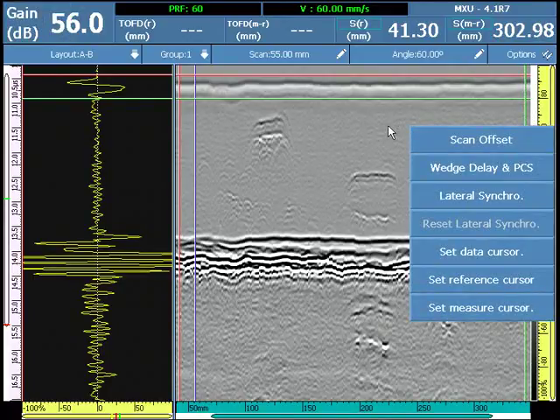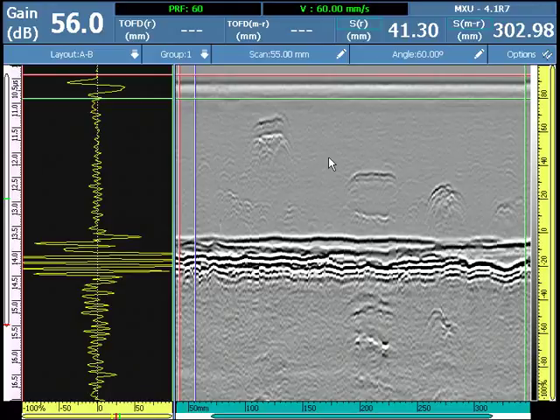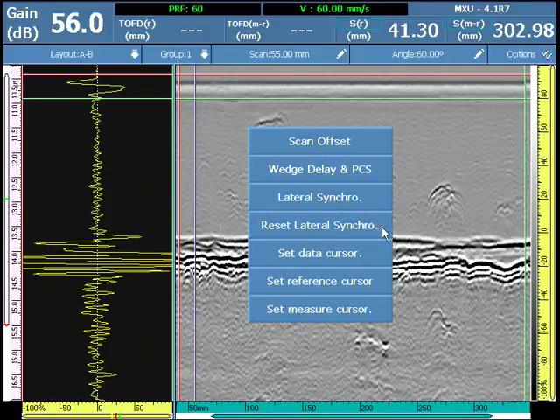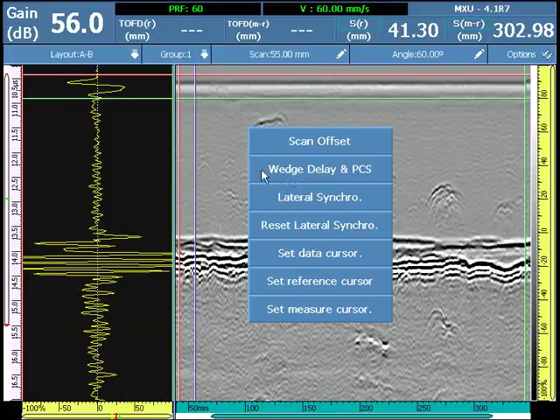select Lateral Wave Synchronization. The software will run an algorithm and modify each A-scan to align it with the reference A-scan seen here. The lateral wave can be reset or re-synchronized at any time.